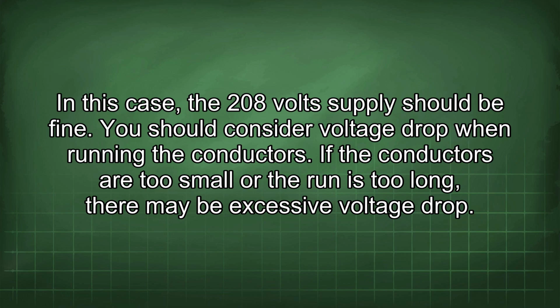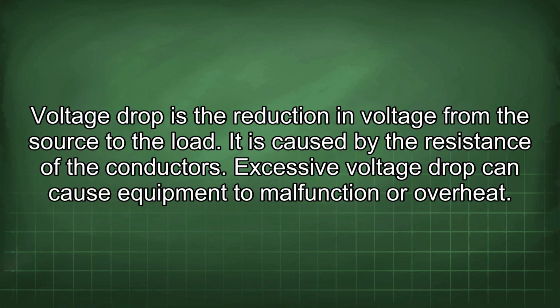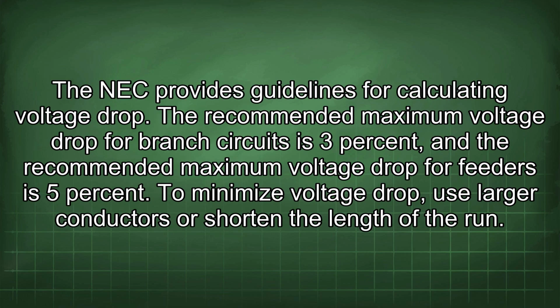You should consider voltage drop when running the conductors. If the conductors are too small or the run is too long, there may be excessive voltage drop. Voltage drop is the reduction in voltage from the source to the load. It is caused by the resistance of the conductors. Excessive voltage drop can cause equipment to malfunction or overheat. The NEC provides guidelines for calculating voltage drop.